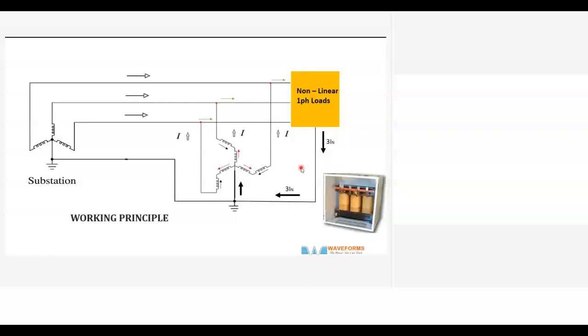So from the load, all the neutral current flows into the winding in this way, and from the power line you get the third harmonics in this direction, and the third harmonics are 180-degree phase shifted, so they cancel out. So the phase gets offloaded, and the neutral wire also gets offloaded. So you will not have any current flowing into the delta of the distribution transformer, heating the transformer, or one particular winding heating up and causing failure.